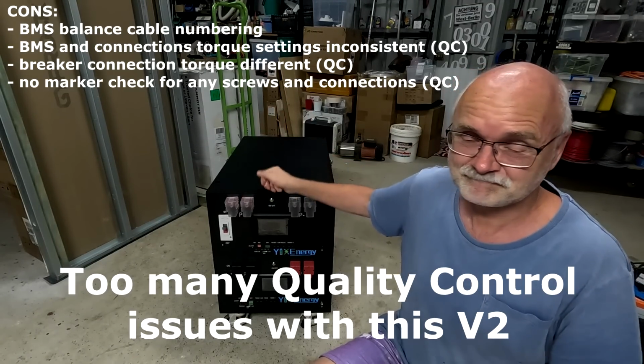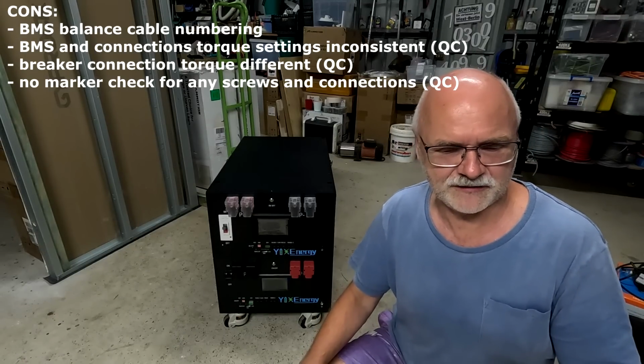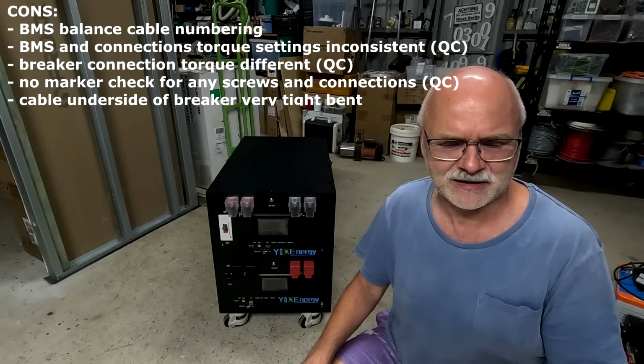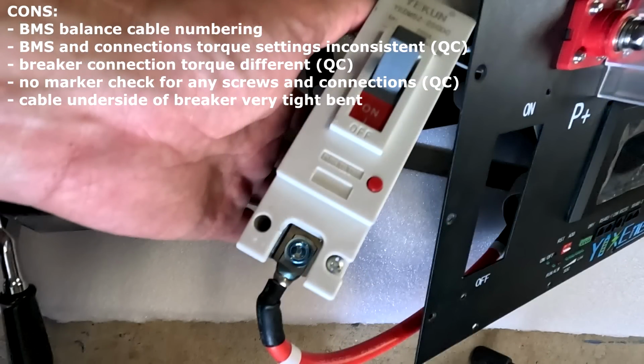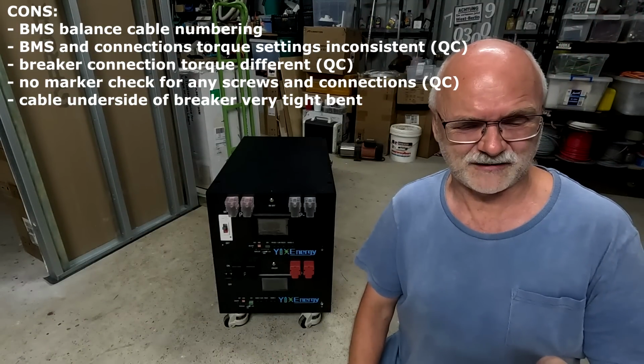I haven't shown this in the video, but the cable on the underside of the breaker actually has a very tight bend in it. It comes out of the ring lug and then bends at a very sharp angle. I don't quite like this, maybe they can find a better way to do that.